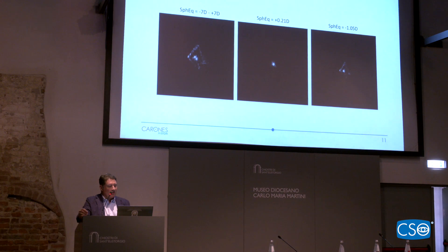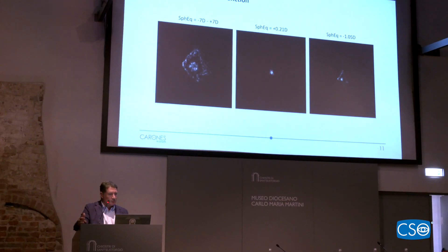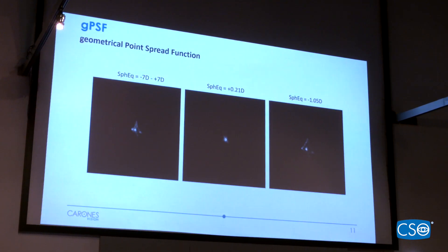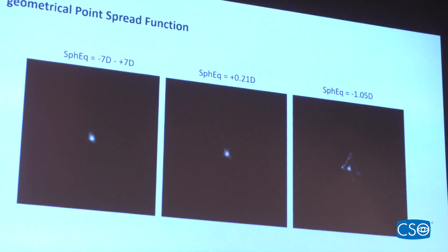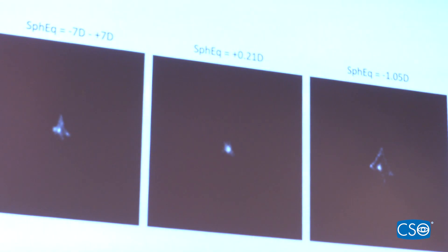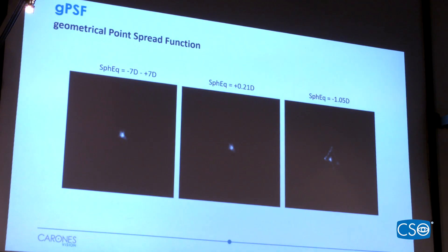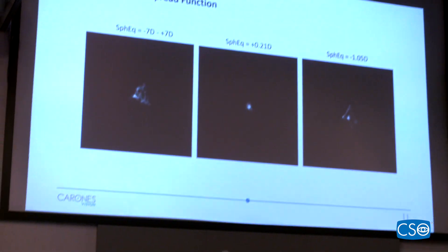On the left side of the slide, you see the measurement of an EDOF lens with the focus curve ranging from around minus seven to plus seven diopters, and you see how the point spread function changes over this entire focus curve. In the two following images, it is possible to identify two specific points where the focus is more concentrated. These two foci are at plus 0.21 diopters and minus 1.05 diopters — meaning it is possible to objectively measure the extension of depth of focus on an EDOF lens.